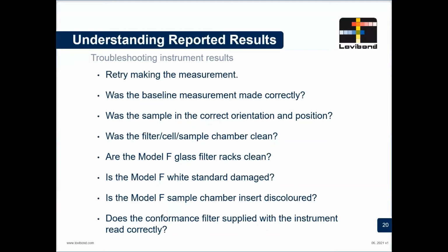Now, are the glass racks clean? Is the white standard nice? Is there no damage in it? Is our sample insert discolored?